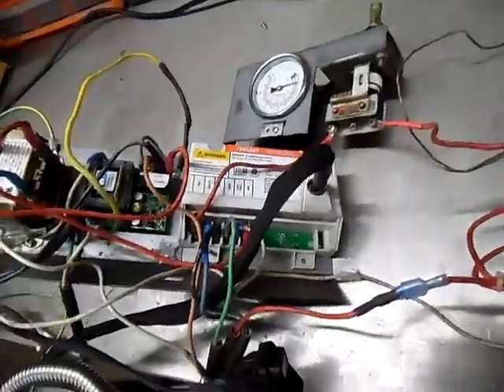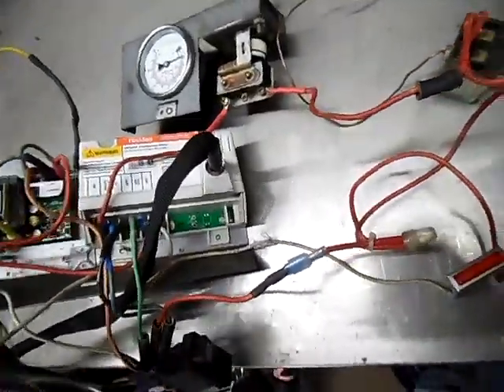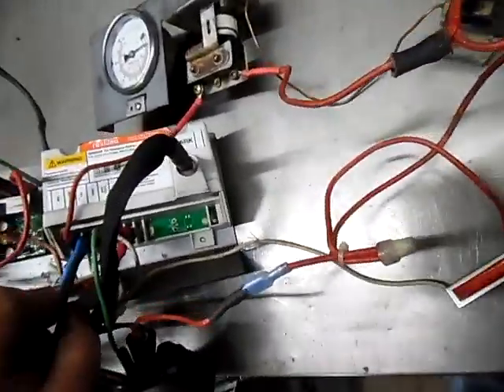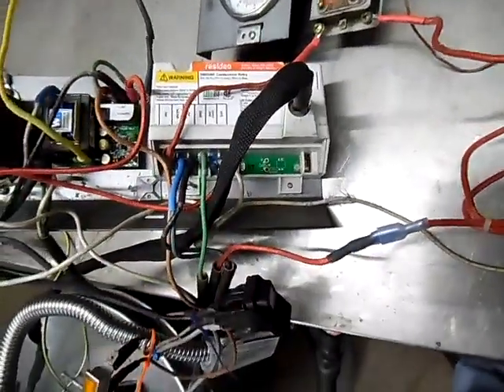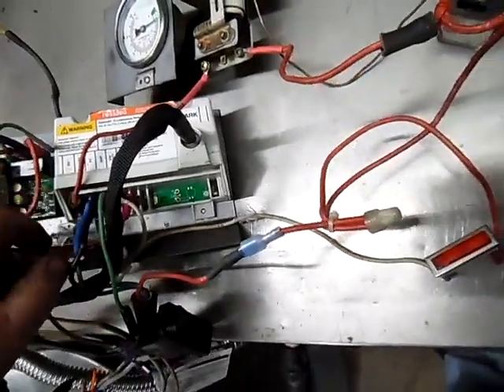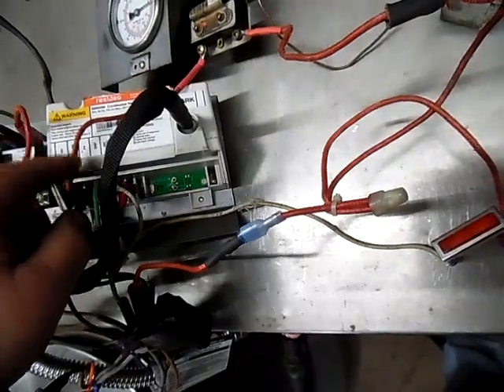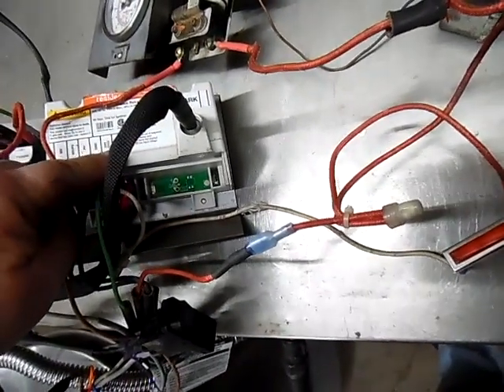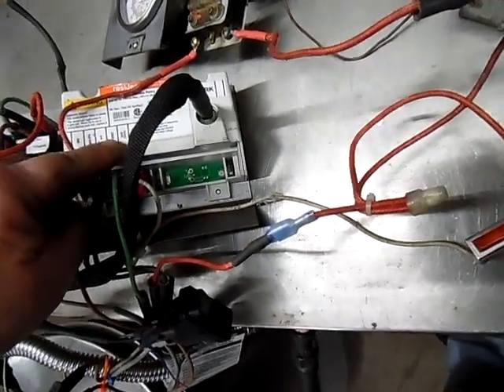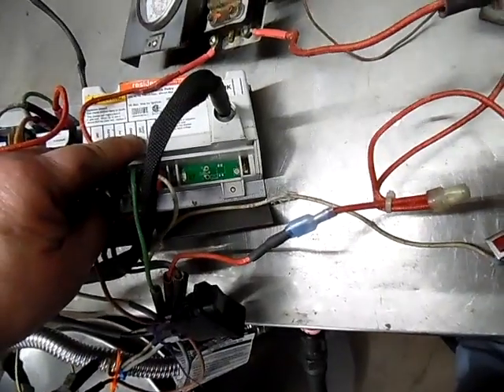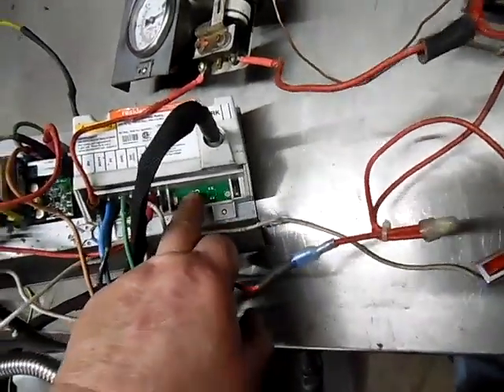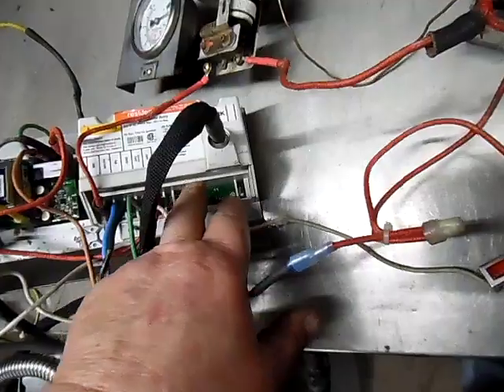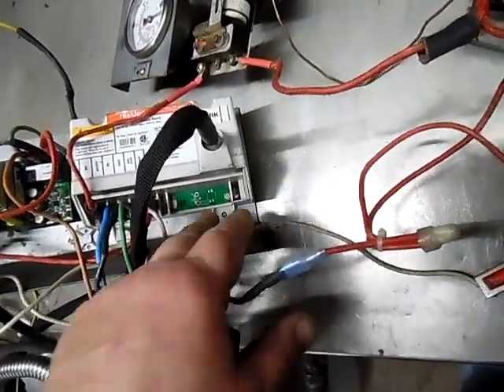This is actually a relatively simple system, because when this energizes, we get 24 volts to here and immediately get spark. So if you're not getting spark, you're immediately going to check that you've got 24 volts positive and a good ground. And on your box, you'll see a little red light. A lot of boxes will have indicator lights telling you it's got power to the box.